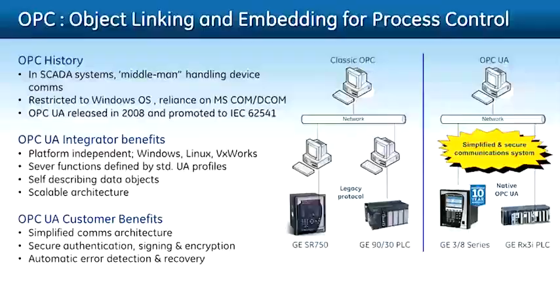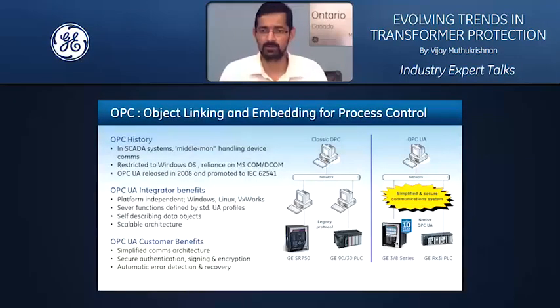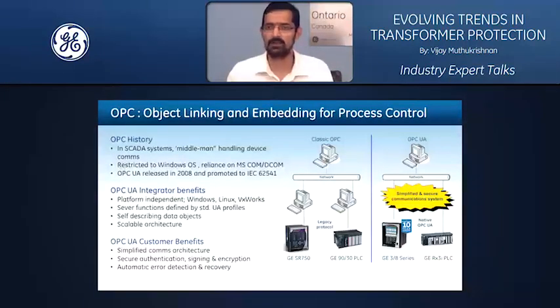But OPC UA has been introduced and has been evolving in the automation industry for quite a few years now. In the continuation of that is the application of that in protection relays. When you really think about a protection relay having OPC UA embedded in it, your ability to self-configure using OPC UA, for instance a CIMPLICITY HMI if you are using one, means you can easily integrate them in a simpler manner. You eliminate almost a layer of devices in your communication architecture. You can add layers of security natively. So there are a lot of benefits by bringing OPC UA into the protection relays itself. This is another unique benefit both the integrating businesses as well as the end users will feel in a product like 845 and the entire 8 series platform.